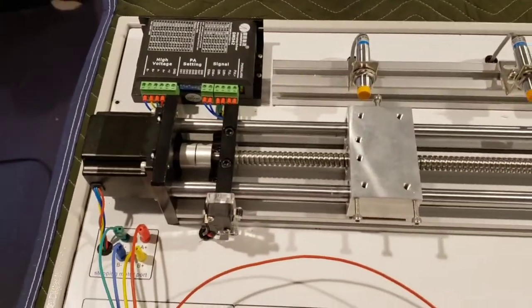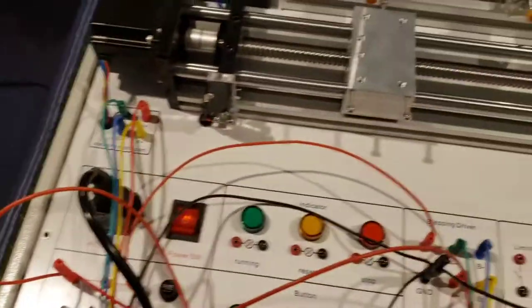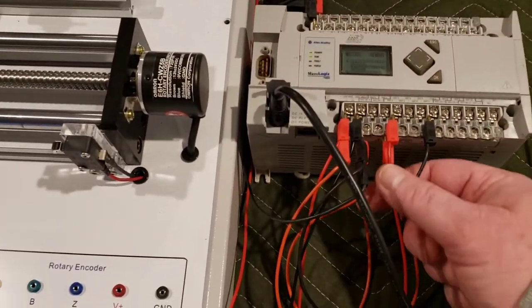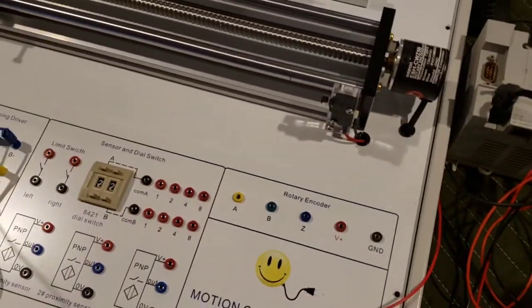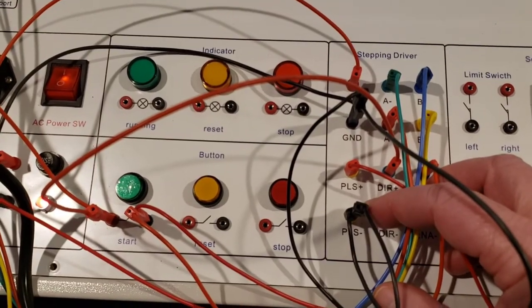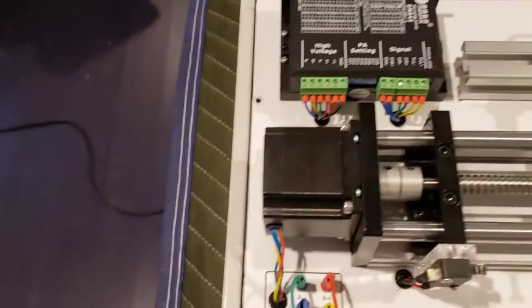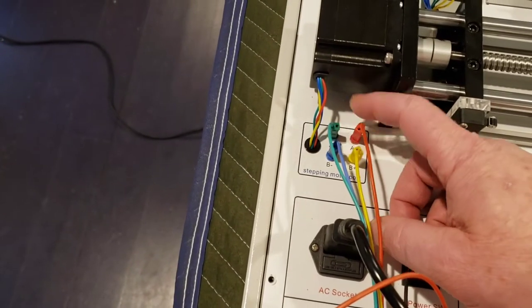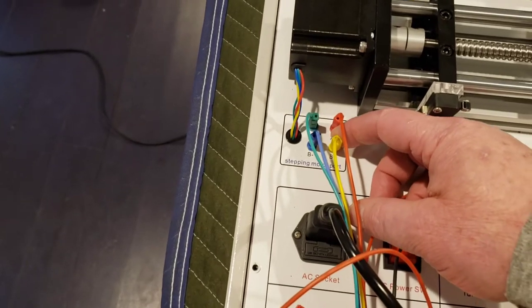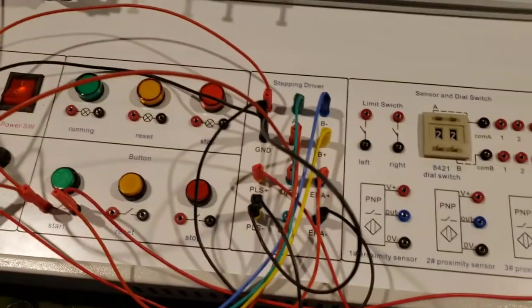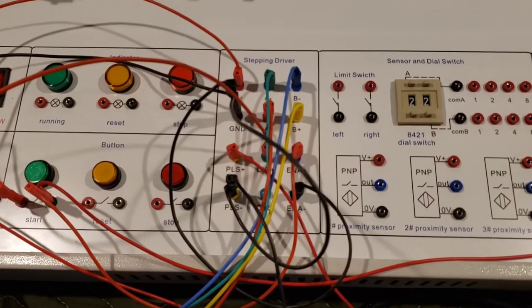Didn't quite make it there, but you're taking pulses from the PLC. In this case we're using a 1400, so output two we're generating the frequency. The frequency is coming into here, and then we're going from here to our stepper drive, then from our stepper drive back to here, then we're wiring it up to our motor. These are a direct input to the motor, so it's all with two millimeter banana plugs, so that way it's easy to play around with and redo and undo. If you mess something up, it's easy to fix.